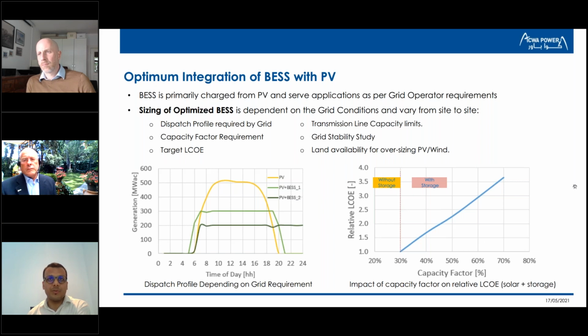Some other points include the grid stability study of the region in terms of PV size, and what the best power and energy capacity to add should be. Also, to achieve a particular dispatch profile, the PV or wind might require oversizing compared to the dispatch limitation. So land availability also becomes a factor in optimizing the best size - whether there's enough land to oversize PV so that transmission capacity isn't breached while the capacity factor can still be increased.